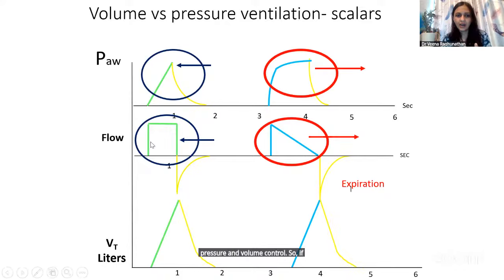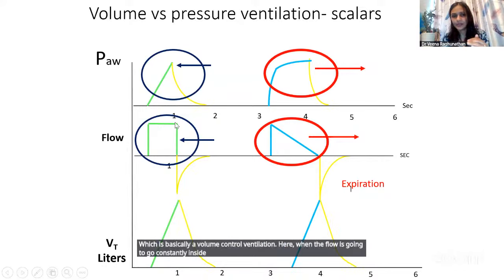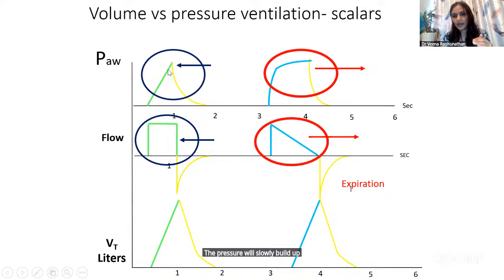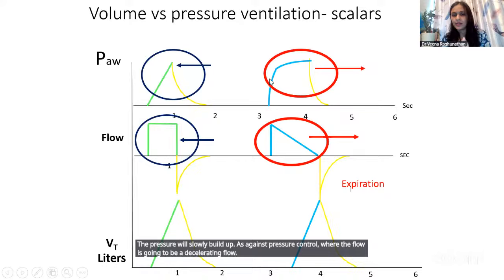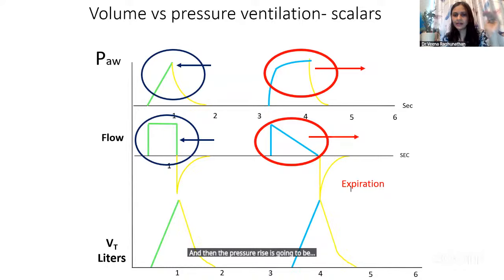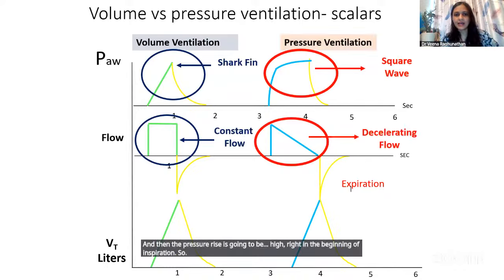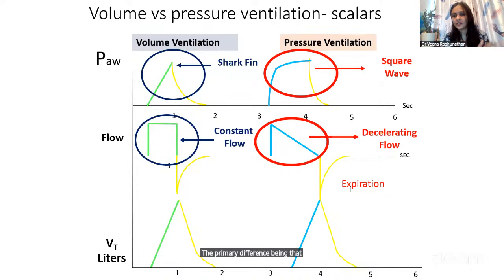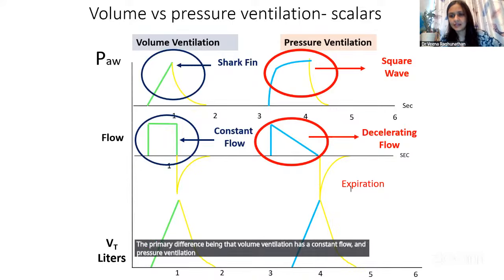So if we see on the right side, we have a decelerating flow pattern. On the left side, we have a constant flow pattern, which is basically volume control ventilation. Here, the flow goes in constantly during inspiration, so the pressure will slowly build up. As against pressure control, where the flow is decelerating and the pressure rise is going to be high right in the beginning of inspiration. So we describe this as a shark fin pattern in volume ventilation and a square wave pattern in pressure ventilation. The primary difference being that volume ventilation has a constant flow and pressure ventilation has a decelerating flow.